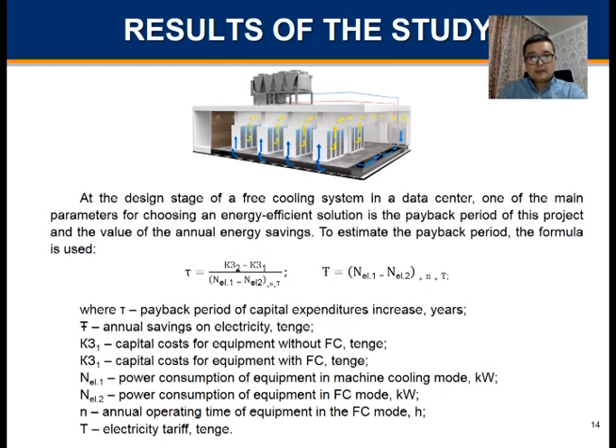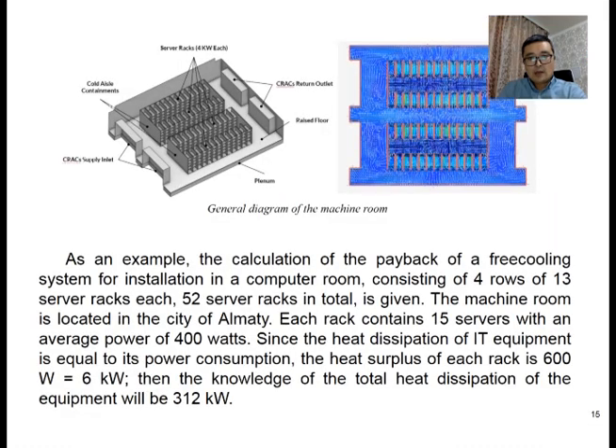Results of the study. At the design stage of a free cooling system in a data center, one of the main parameters for choosing an energy efficient solution is the payback period of the project and the value of the annual energy saving. To estimate the payback period, a formula is used. As an example, the calculation of the payback for a free cooling installation in a computer room consisting of 4 rows and 13 server racks each, 52 server racks in total, is given.